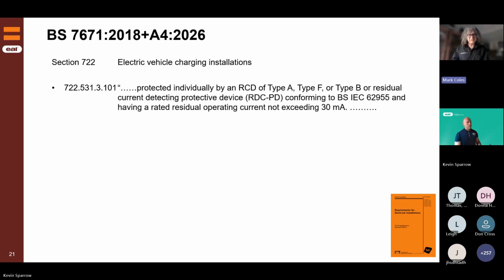So where I'm going with this is in 531.3.101 in 722. It says that unless supplied by a circuit using the protective measure of electrical separation, each charging point incorporating a socket outlet, blah, blah, blah, shall be protected individually by an RCD. So what this is talking about is RCD protection for circuits and equipment charging electric vehicles.